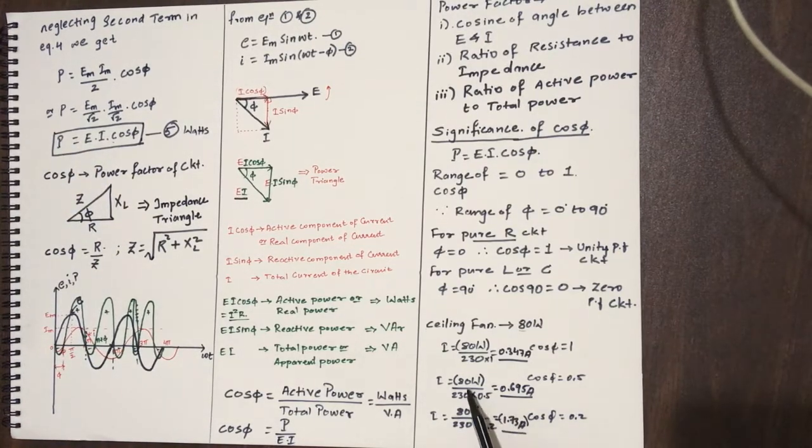Now for the same load, if the current drawn is more because the power factor is less, then the installed conductors are drawing excessive current, which may deteriorate the life of the conductors and the life of the associated insulators. It in turn is burdening or overloading the currently installed power system. Therefore, with the choice of lower power factors, we are overloading the system because of drawing an excess amount of current.